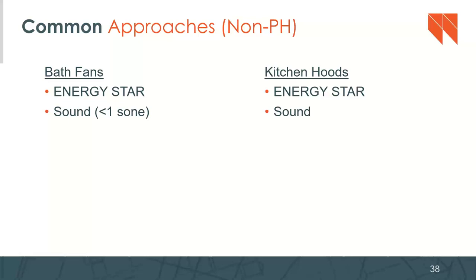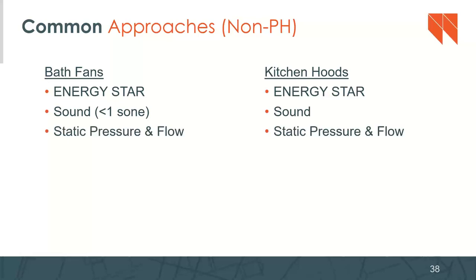as part of that spec to earn the Energy Star for a bath fan itself, they've got to have a sound level that is less than 1 sone. They're also going to be tested for static pressure and flow, which is a huge deal. It goes to the point that the other question was about: does the system actually have to perform? Well, when you buy an Energy Star rated piece of equipment, you can see those static pressures and the corresponding flow rates for them.